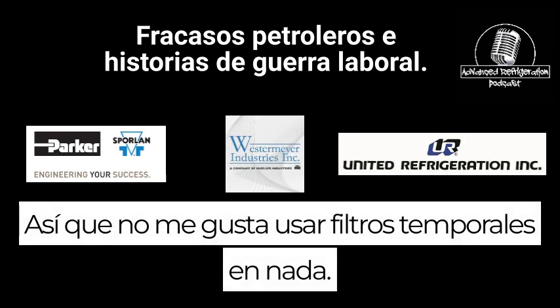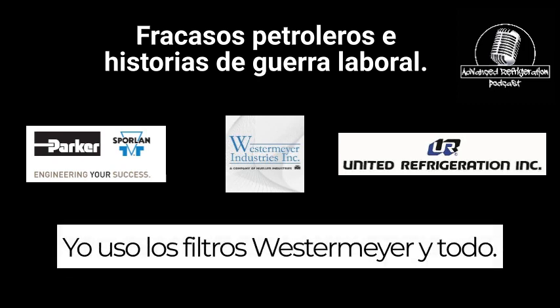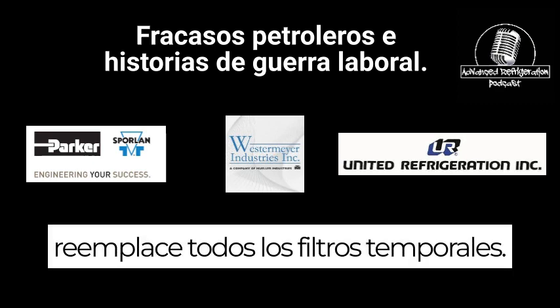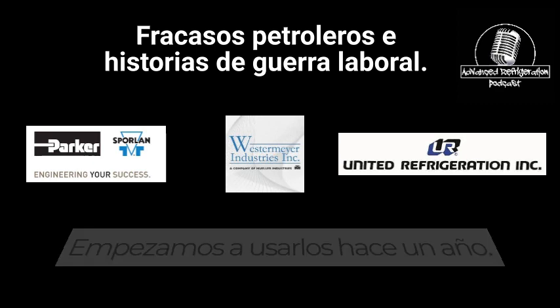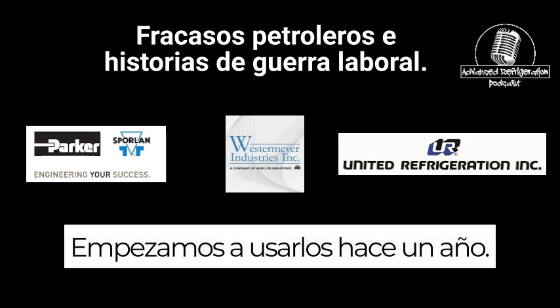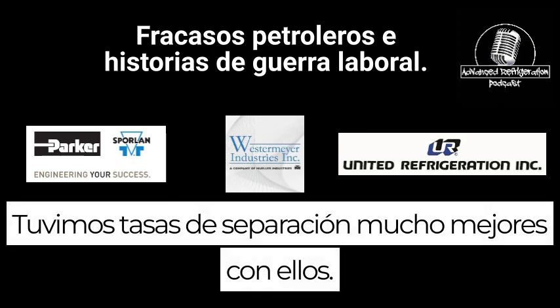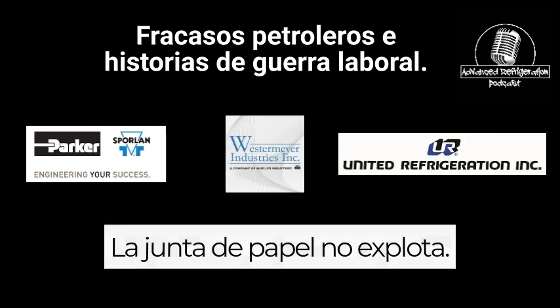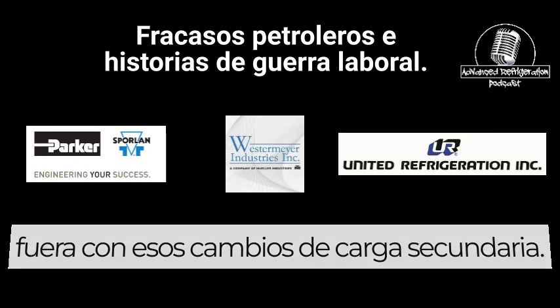So I do not like to use Temprite filters in anything. I use the Westermeyer filters in everything. Westermeyer makes a filter to replace every single Temprite filter. We started using them a year ago. We had way better separation rates with them, and they have a paper gasket at the bottom. The paper gasket does not blow out with those sudden load changes.